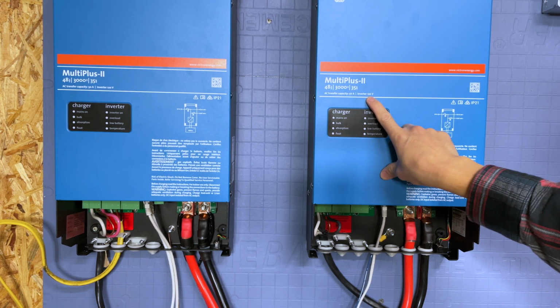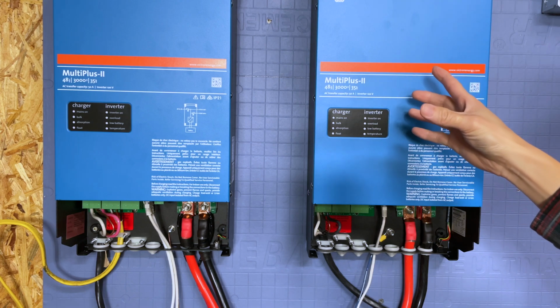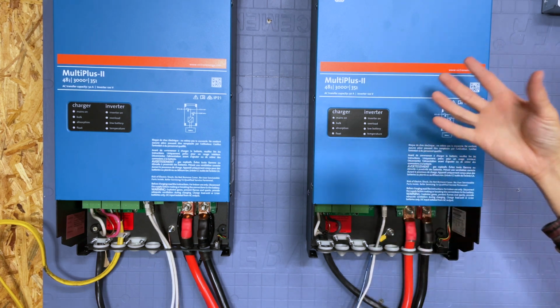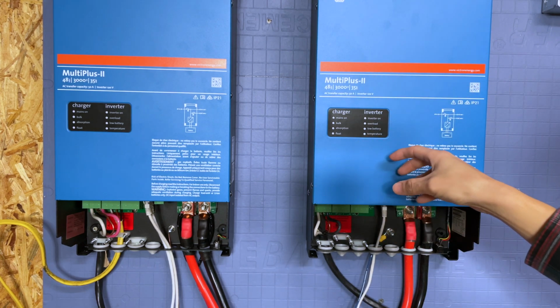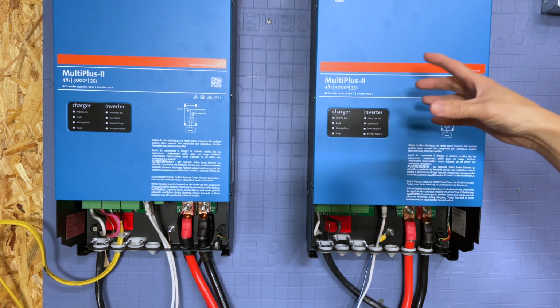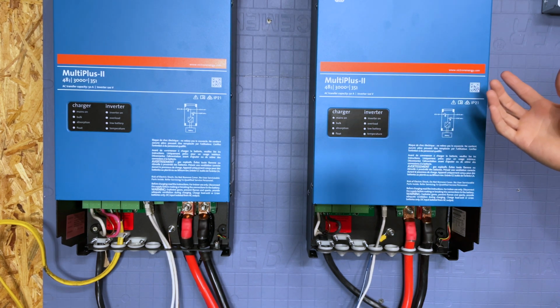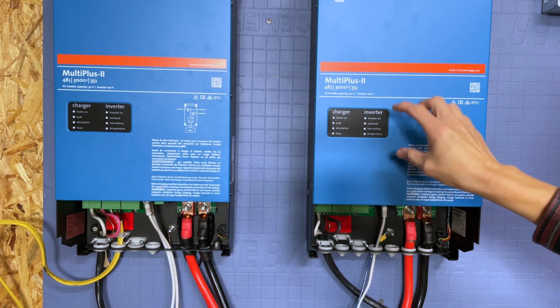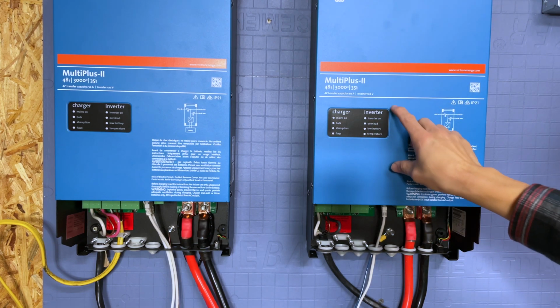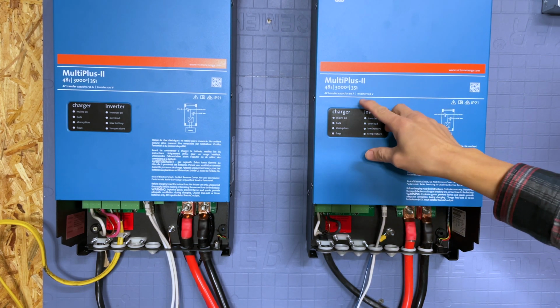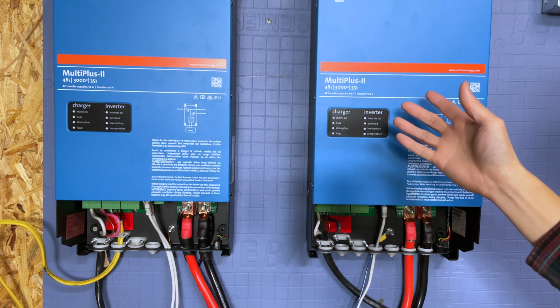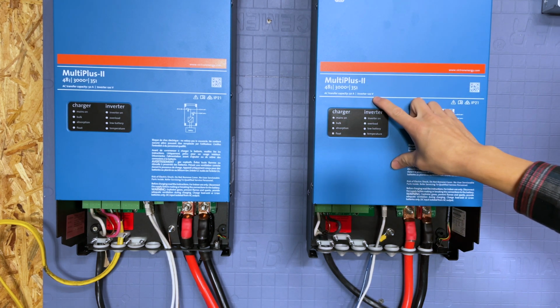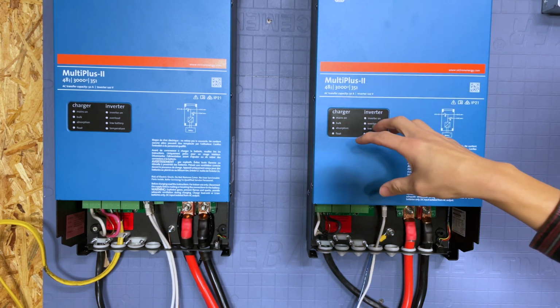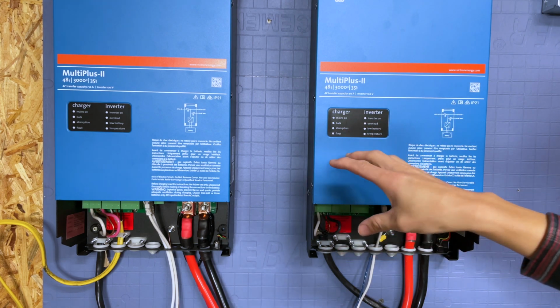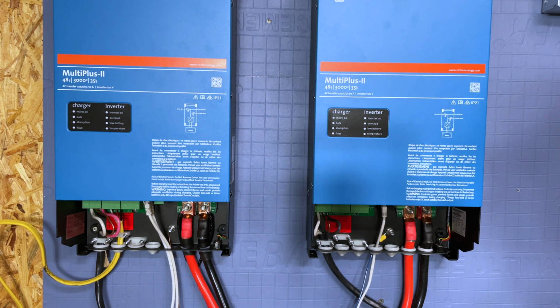This is a 120 volt inverter. If you're shopping around for Victron inverters, make sure if you're in the US you're looking at the US model, and if you're elsewhere like Europe, make sure you're looking at the European model, since they make 230 volt units for Europe and 120 volt for the US. You can technically get the 230 volt in the US, but you'll probably need to step it down using an auto transformer - that's a more advanced setup we'll probably cover later.